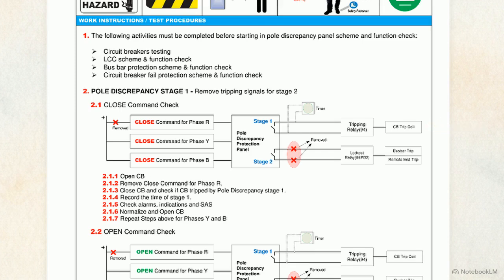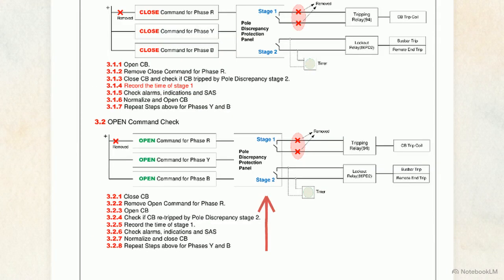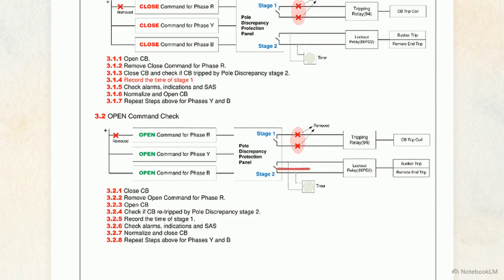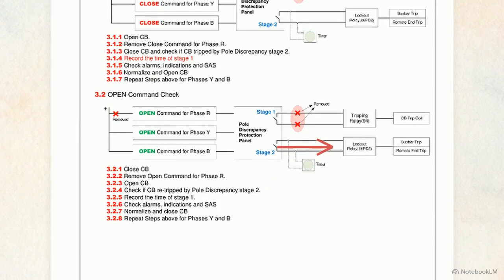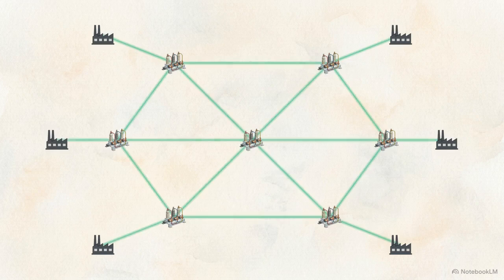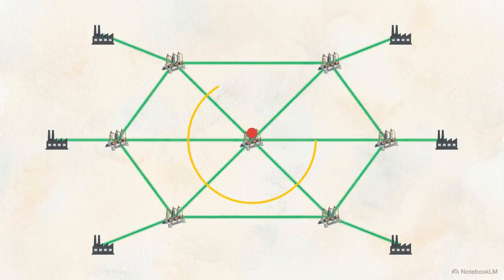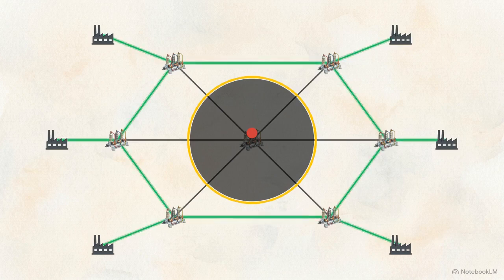If the local trip fails, this Stage 2 schematic outlines the escalation path. The system triggers the 86PD2 lockout relay to initiate a full busbar clear and remote end trip. Verifying these cascading lockouts ensures a localized mechanical failure is isolated before propagating into grid-wide instability.